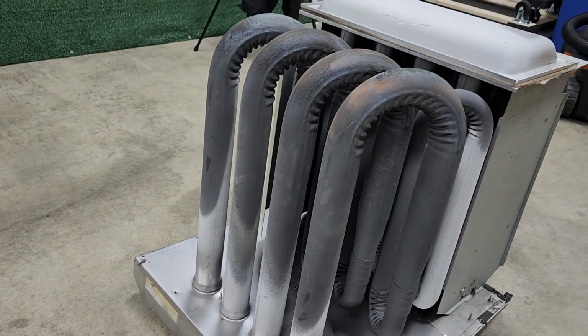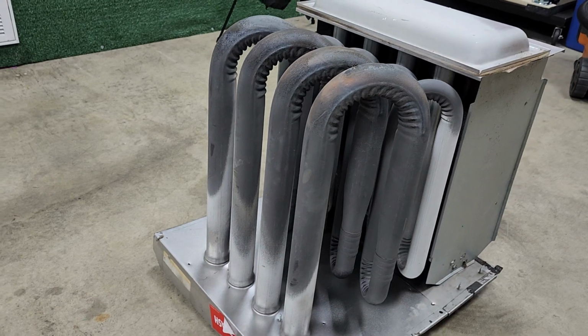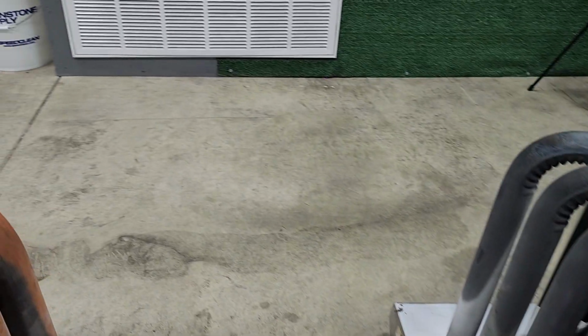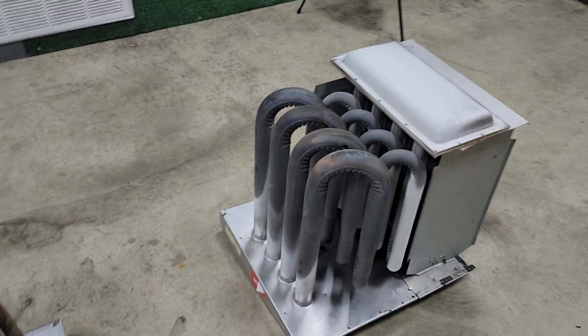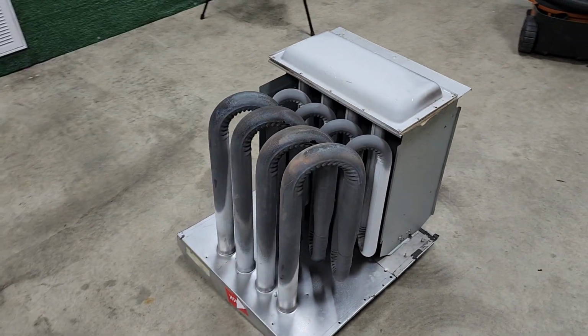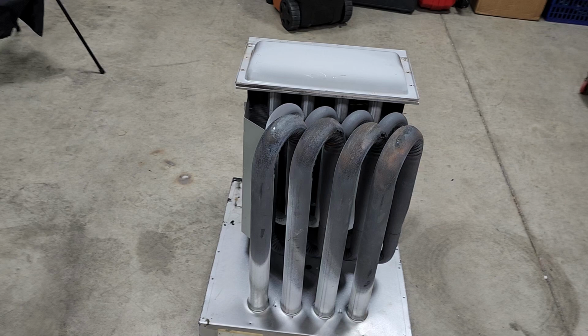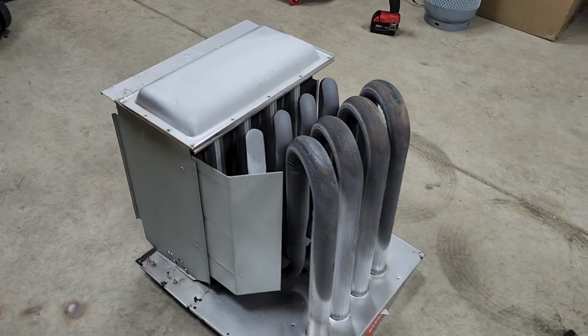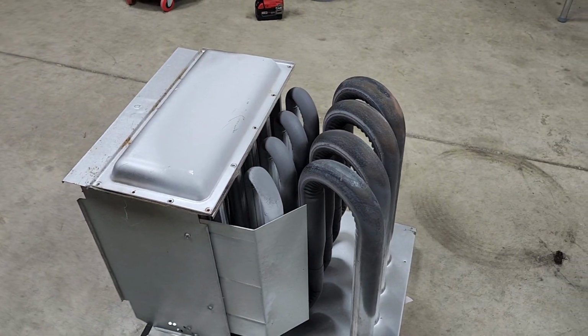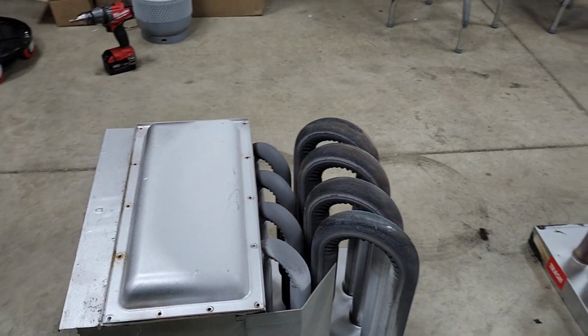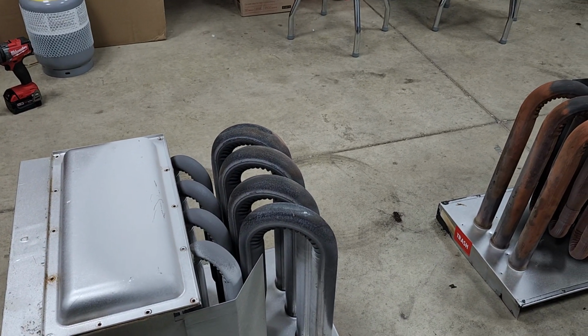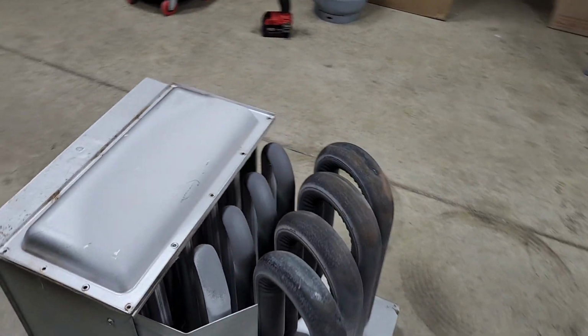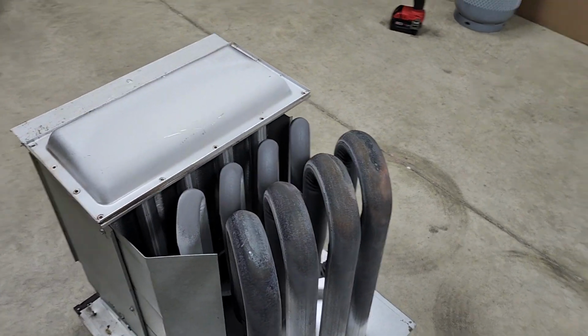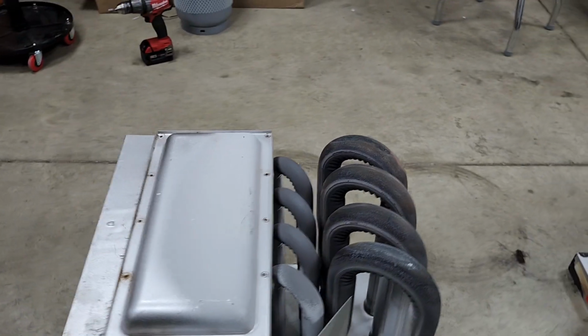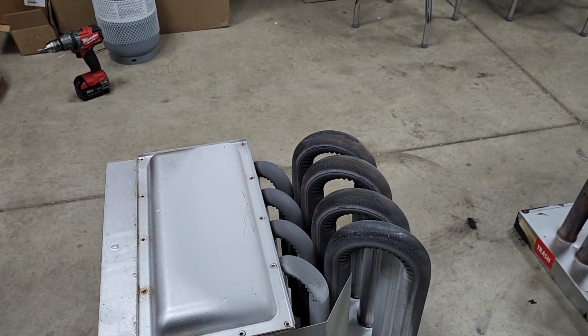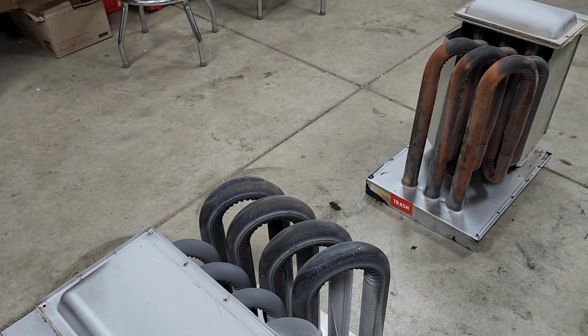And a couple of ways to prevent this is, number one, simply setting your gas pressure. Every time you do a service call, every time you do an install, I always recommend you set your gas pressure, or at least check it every time you're there for a visit. That's going to help you determine if we're going to overfire this furnace or not. And the other thing is an airflow check. Do your static pressure checks. Make sure that we're moving the correct amount of air across this heat exchanger so that it doesn't overheat.